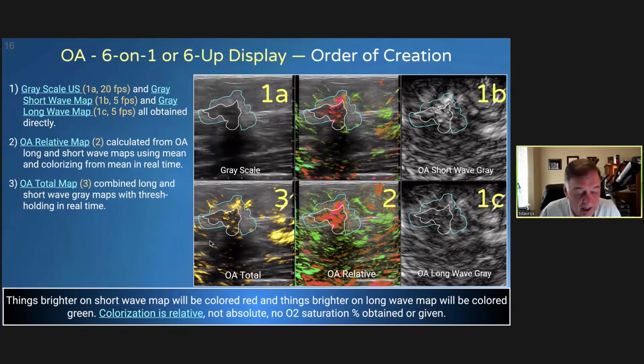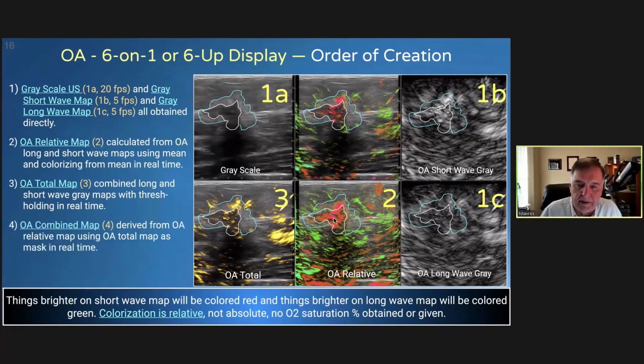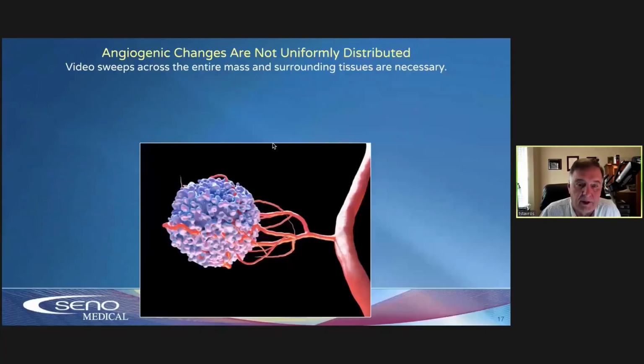It actually adds all the hemoglobin together and creates a total hemoglobin. And then that's used as kind of a subtraction mask on top of the OA relative to create the OA combined. And all this is happening in real time. This is being generated in real time at 5 frames per second in OA. The ultrasound frame rate obviously is going to be faster. It can be 15 to 30 depending on depth and settings like spatial compounding and speckle reduction.